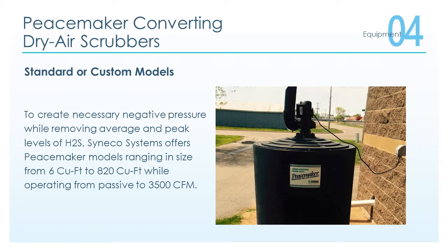Peacemaker converting dry air scrubbers come in standard or custom models. Our objective is to create the necessary negative pressure while removing average and peak levels of H2S. Syneco Systems offers Peacemaker models ranging in size from 6 cubic feet to 820 cubic feet, while operating from passive to 3,500 cubic feet per minute.